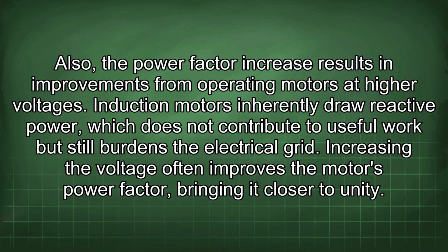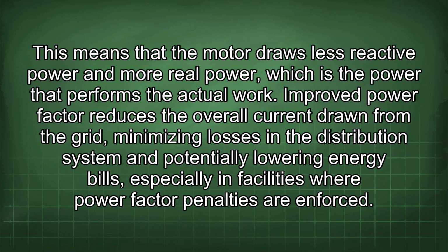Also, the power factor increase results in improvements from operating motors at higher voltages. Induction motors inherently draw reactive power, which does not contribute to useful work but still burdens the electrical grid. Increasing the voltage often improves the motor's power factor, bringing it closer to unity. This means that the motor draws less reactive power and more real power, which is the power that performs the actual work. Improved power factor reduces the overall current drawn from the grid, minimizing losses in the distribution system and potentially lowering energy bills, especially in facilities where power factor penalties are enforced.